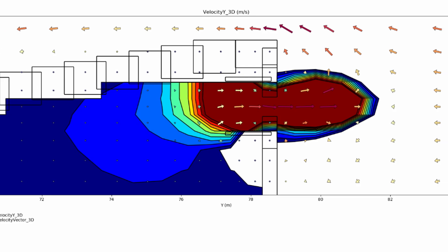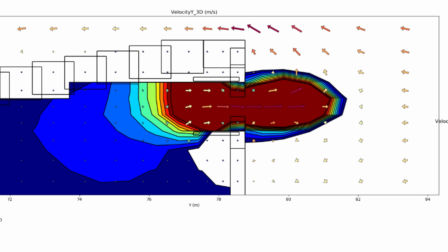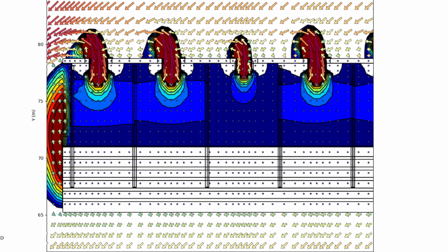This is something A-Solutions has done for a very long time. With our modeling team, what we're finding is these models are creating some surprising results. Gases, particularly indoors, do not behave necessarily in an intuitive way. Where an expert might think is a good location for a detector, the gas may go undetected — it may not collect in sufficient quantities in that location.